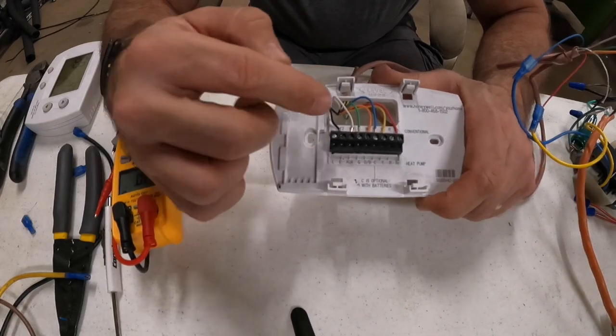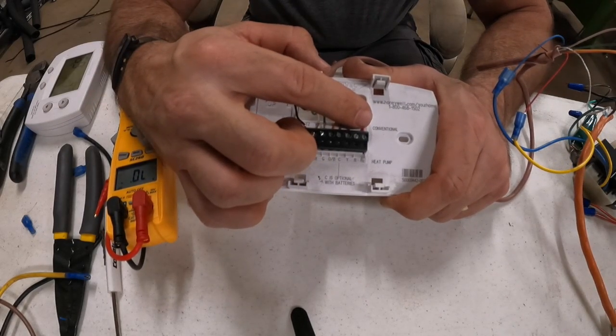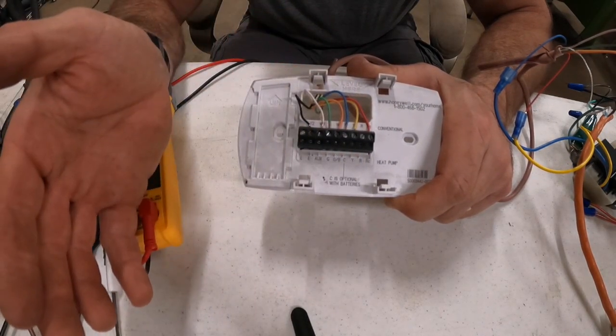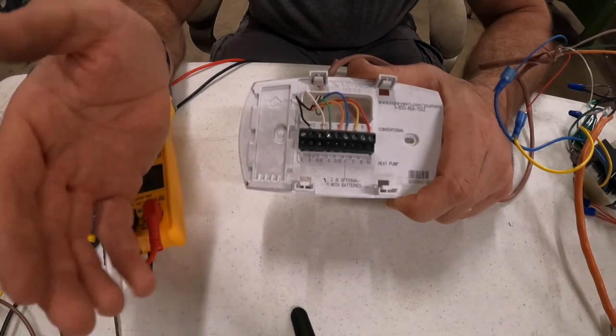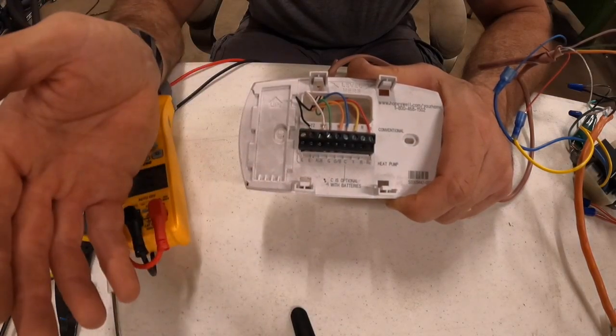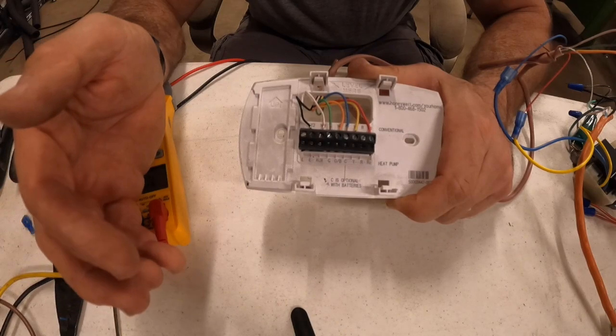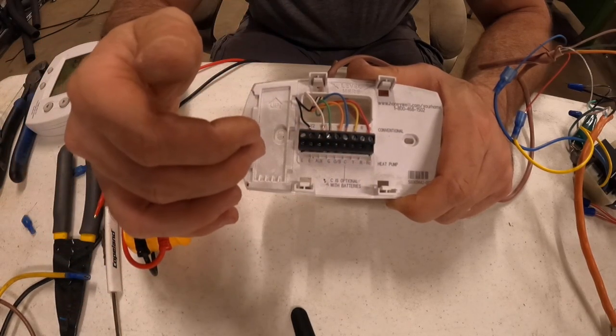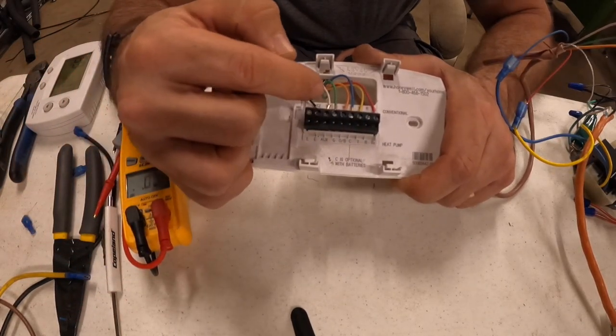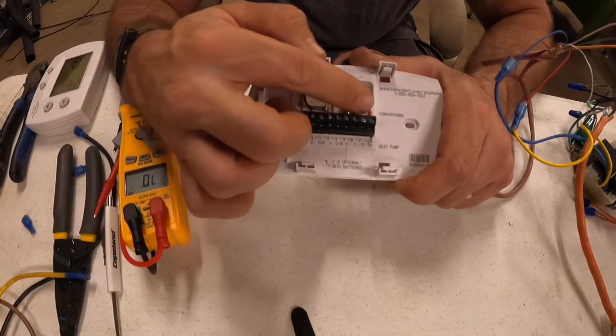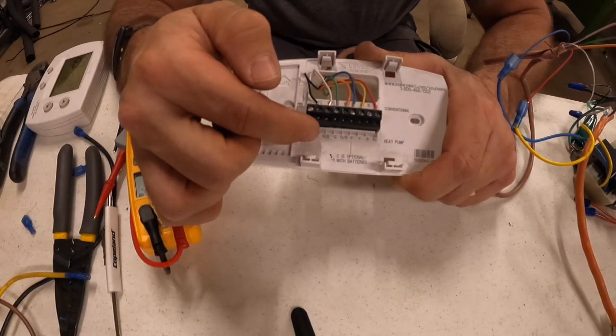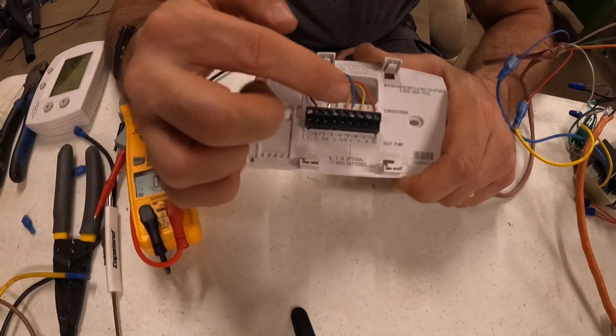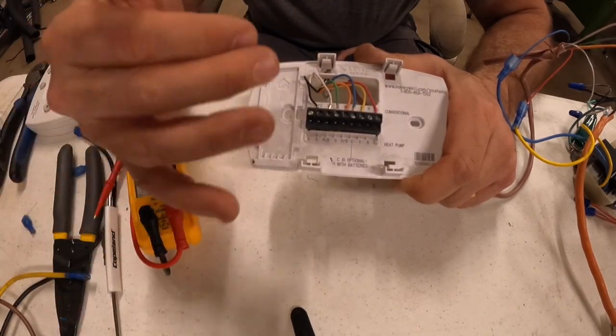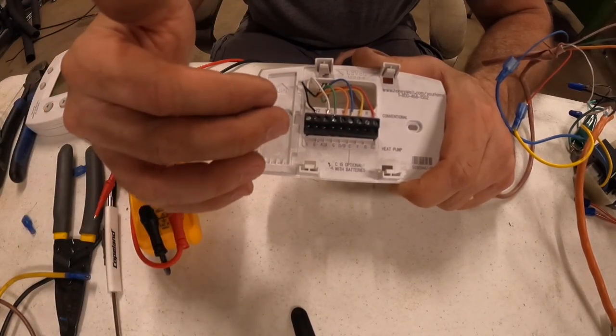And this can be used for a conventional system, which is electric heat with an AC, or gas heat with an AC. That can be propane or natural gas. This thermostat can be used with a variety of things, but you have a wiring designation up here for conventional systems and one on the bottom for heat pump. I've got this wired up, or I'm going to configure the thermostat, for a heat pump.